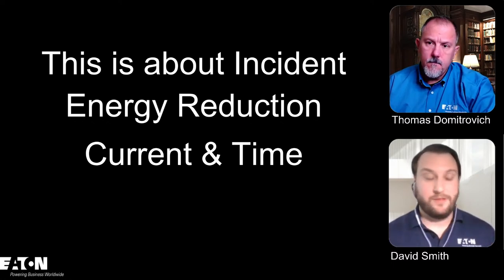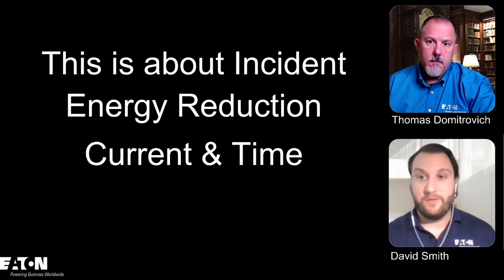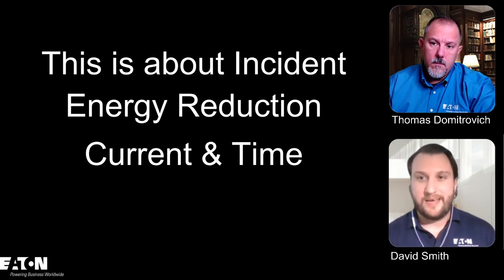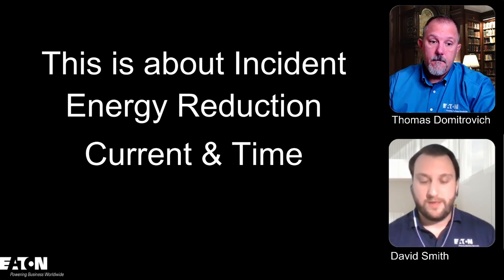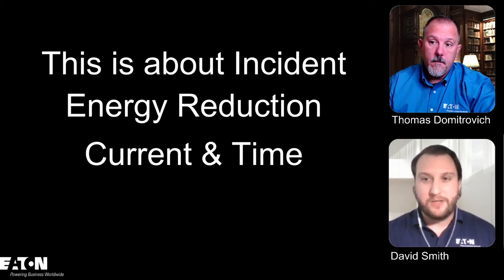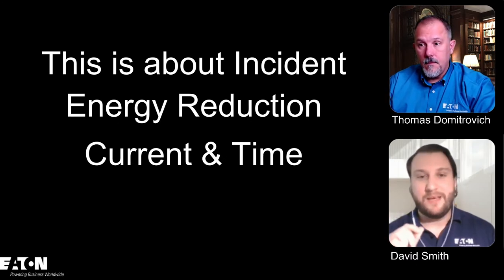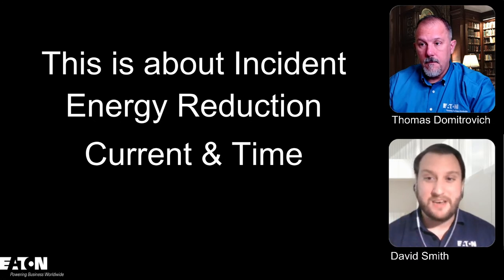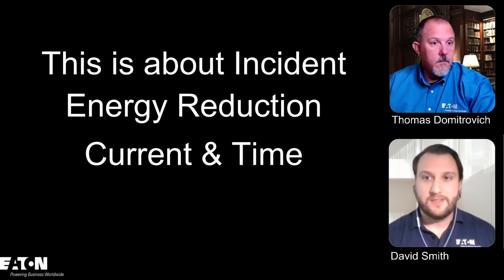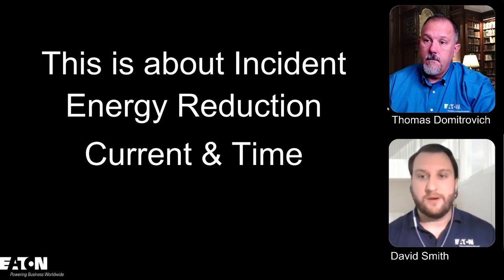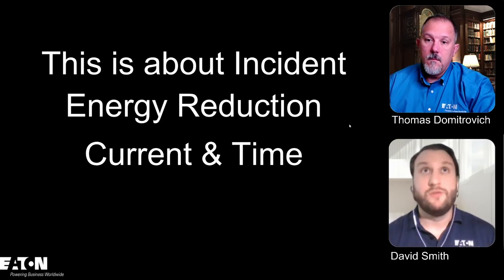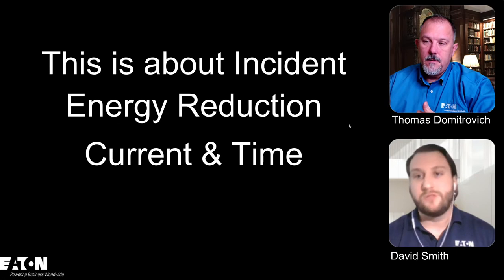So for maximum current, you would assume that all the motors are on. What we're really looking at today is all the motors off, for the minimum arcing current, because we're not necessarily talking about the maximum energy making the breakers flip as quick as they can. It's the possibility of them not necessarily being slow, but not being fast enough, so that there could be an event where we just want to make sure everything's covered. And this is really what Article 240.87 is talking about, which is what we're going to be talking about tonight.